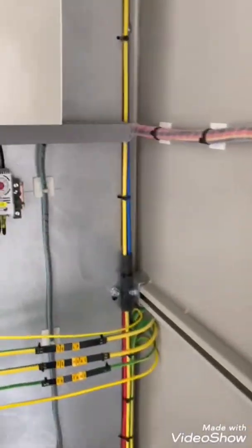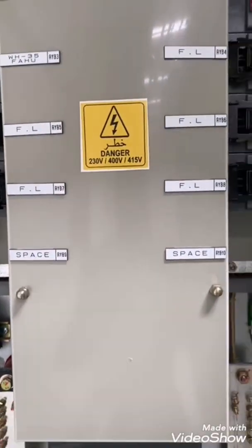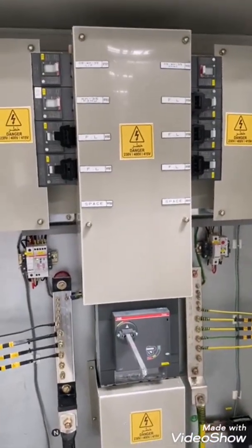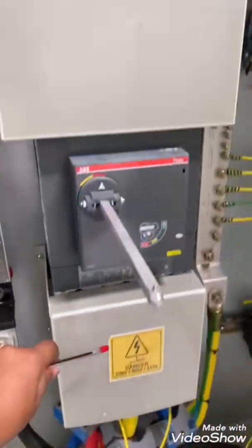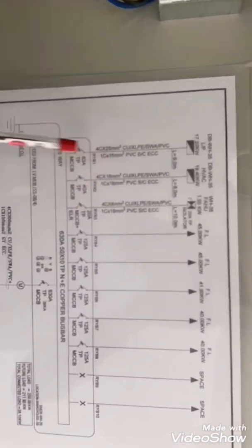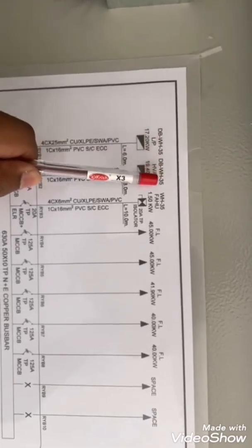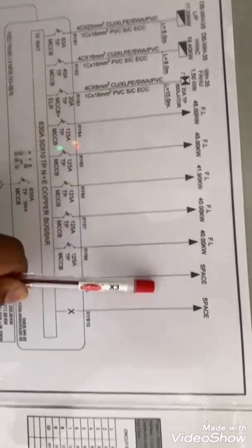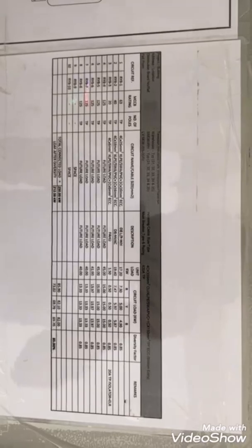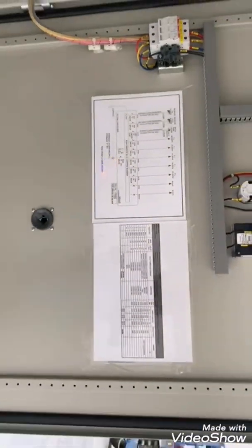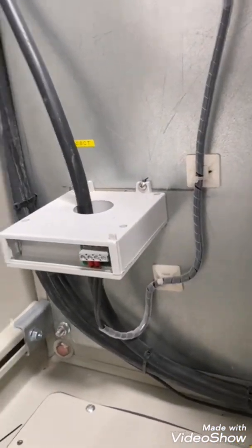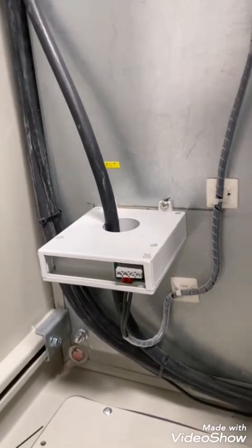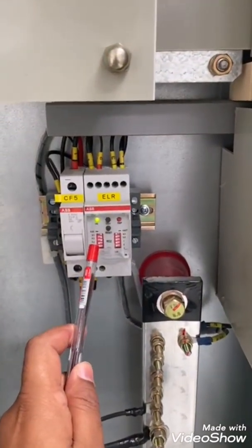Here you can see the CBCT. You will also find some fuses — these fuses are for the protection of the ammeter and voltmeter, and this fuse is for the protection of the thermostat. Behind this protection cover there is a busbar for R phase, Y phase, B phase, and neutral, and there is also a CT behind it for the ammeter. Here I put the load schedule and the schematic diagram — this SMDB is feeding Warehouse 35 DB, including light and power DB, HVAC DB, FHU control panel, and others are spare for future tenants.